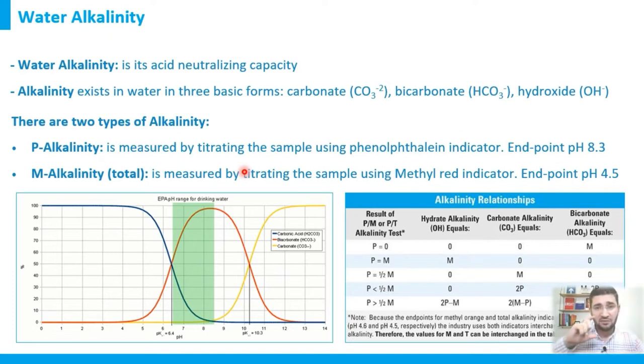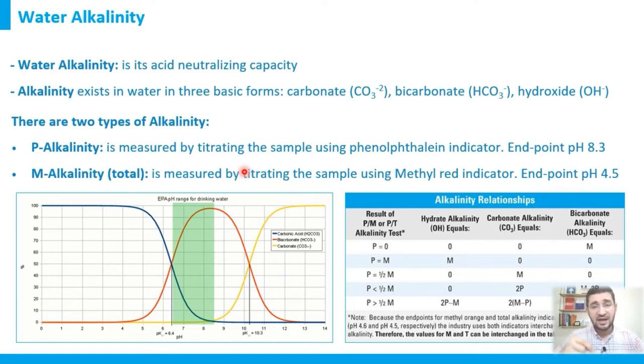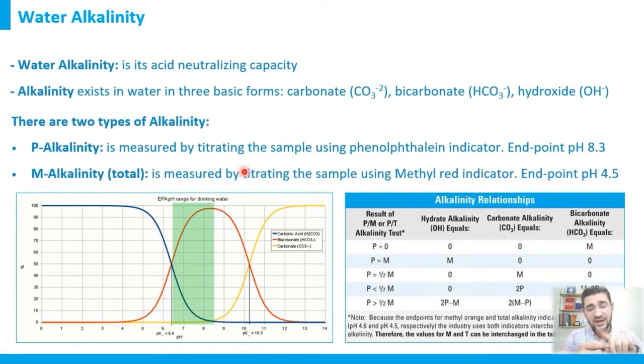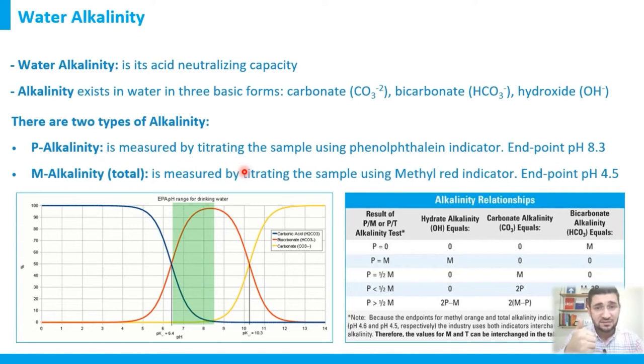For example, if we take a water sample and add a few drops of phenolphthalein indicator, then titrate with sulfuric acid, a color change from pink to colorless indicates that we have neutralized all the P-alkalinity present in the water. This is the first type of alkalinity.